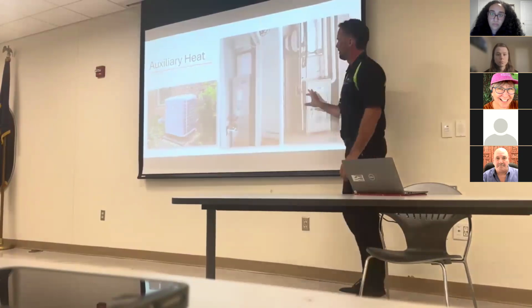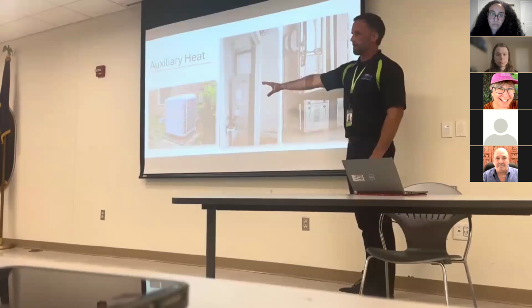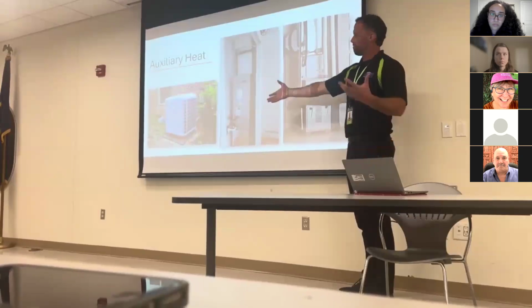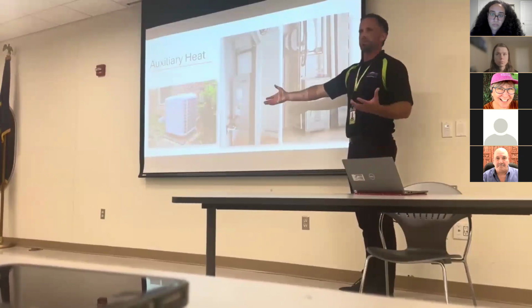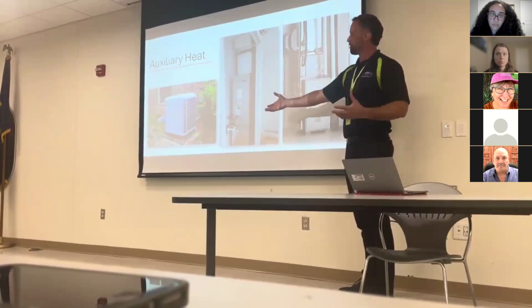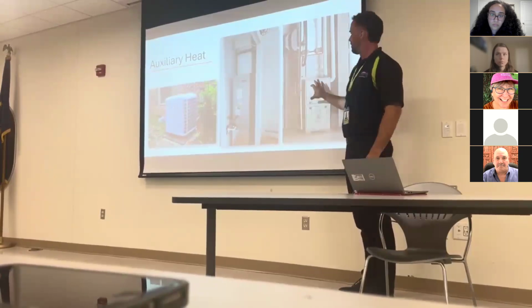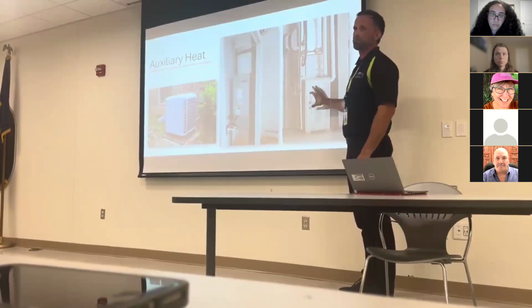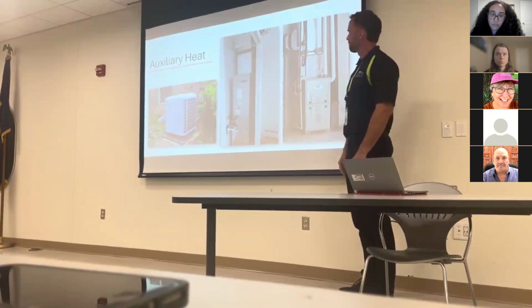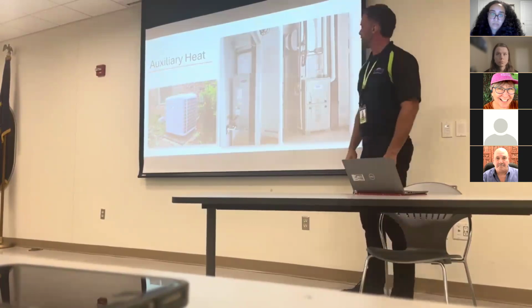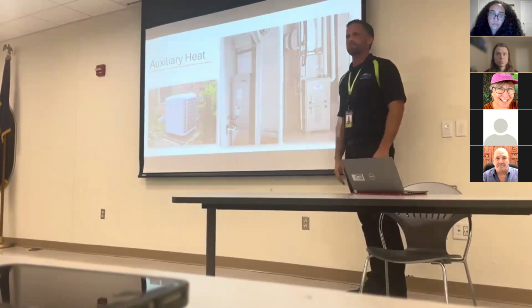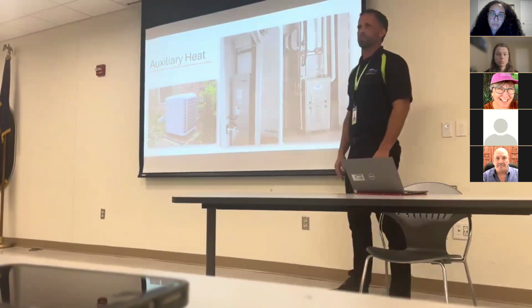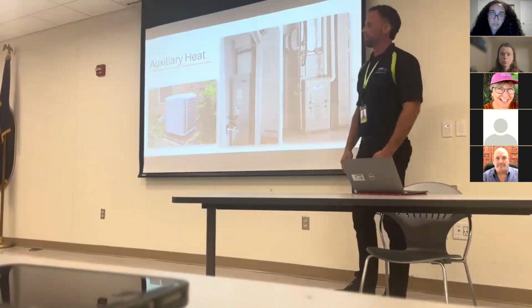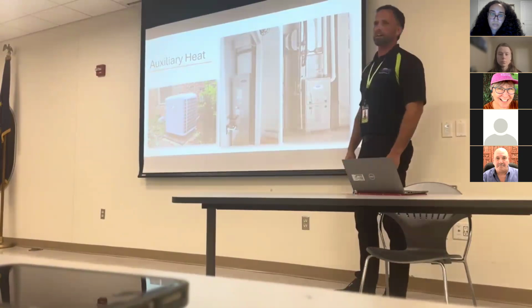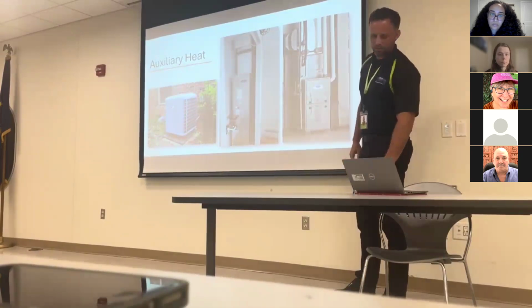With a gas furnace, the heat pump would run primarily, and then you have a balance point set, some outdoor temperature where once it gets below that temperature, the heat pump shuts off and the gas furnace takes over until the outdoor temperature gets back above your balance point. But you compare it with an oil furnace. Anybody have an oil furnace? We're getting few and far between in this market, but oil, LP or propane, you compare it with pretty much anything.